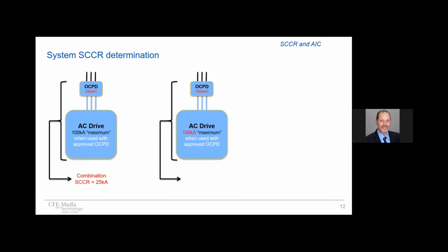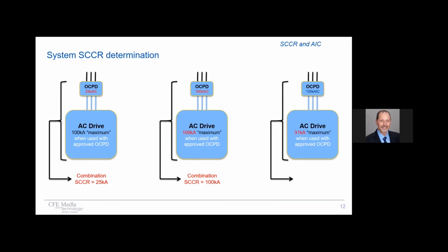Let's take another look at another example. Here we've got both devices rated at 100,000 amps. The drive has a 100,000 amp SCCR, and the breaker or fuse has 100,000 amps interrupting capacity. So in this case, the total system has a combination withstand rating of 100,000 amps. Let's look at one more. In this case, we've got a drive that has a lesser withstand capability. It can only withstand a maximum of 31,000 amps when used with a protective device. But yet we're feeding it with a protective device that has an interrupting capacity of 100,000 amps. In that case, still, it's the lesser of the two for the combination withstand rating. Okay, so quite simply, the SCCR becomes the lowest of the component ratings.